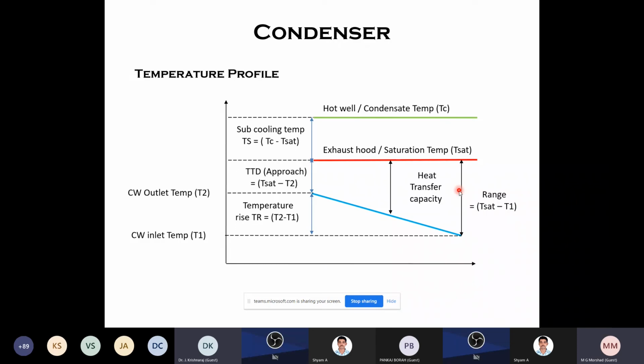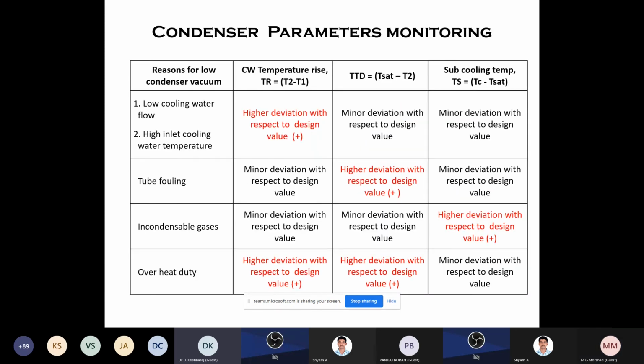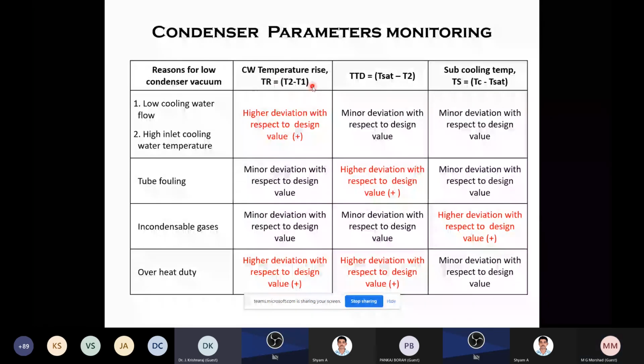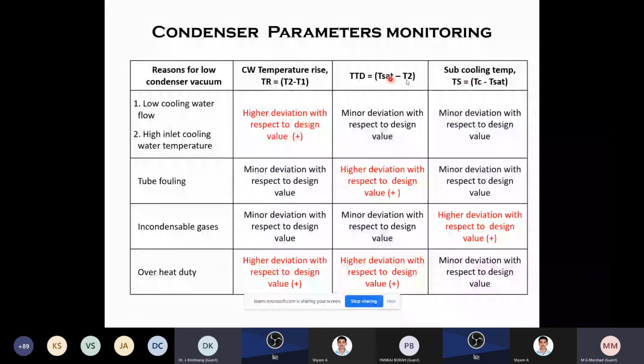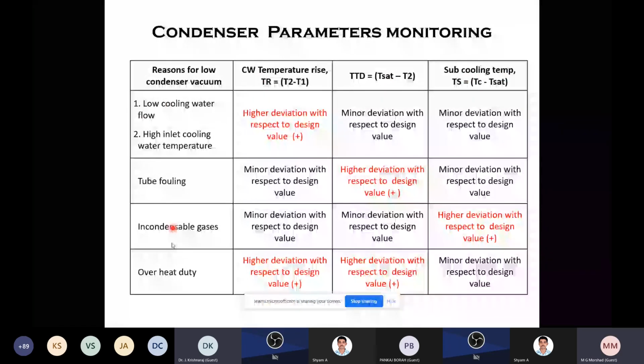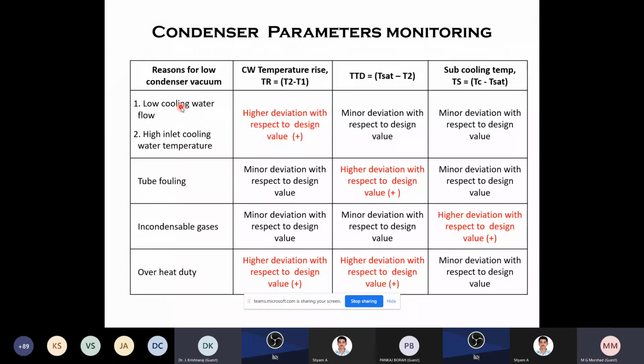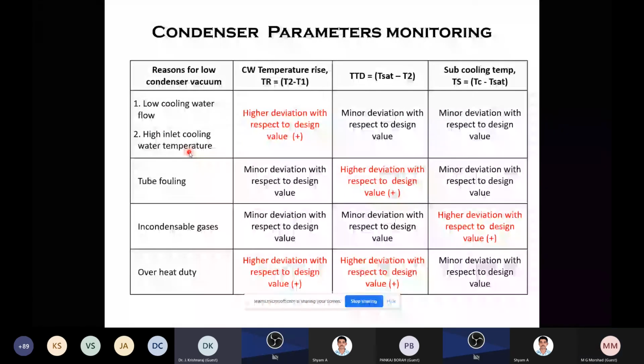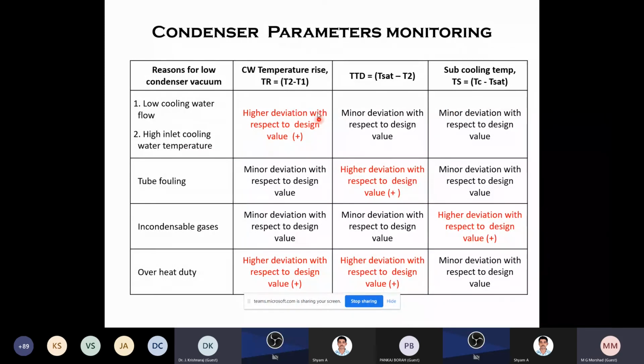So these parameters are available in the control room, and you can take all the parameters and plot a graph like this. Circulating water temperature rise, then TTD and subcooling: these three factors you plot. And these are the reasons for low vacuum. First, the reasons for low condenser vacuum are low cooling water flow or high inlet cooling water temperature, for example due to climatic conditions. If you measure all these, there will be a heavy deviation in the temperature rise while the others remain the same. At that time you can say it is due to these two conditions.